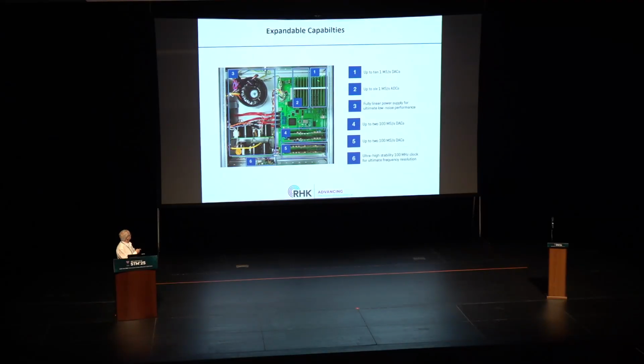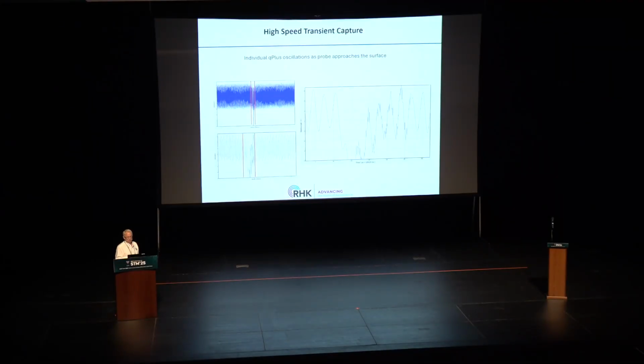So some of them run at 1 megasample per second. Then we have a couple channels that are running at 100 megasamples per second, which for high-speed operations will give you 10 nanosecond time resolution on your measurements. So an example of that, we were running in Q+ mode, and it approached too fast and hit the surface, and you see a little spike in the force. Well, the data density is enough. You could zoom in on the spike, zoom in again, and you're seeing the individual oscillations of the tuning fork, where it whacks the sample, excites the second eigenmode, and you can see it as it decays.